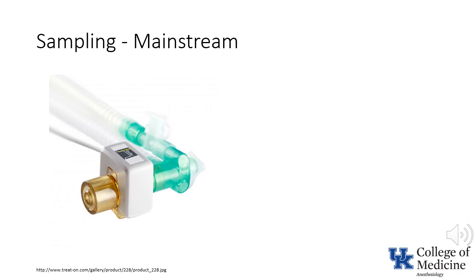The primary advantage of mainstream capnometry is the response time — you see the value almost immediately. Have you ever held your breath waiting for a CO2 waveform after a particularly difficult intubation? You wouldn't have to wait so long if mainstream sampling was used. The primary disadvantage is that the measuring device, attached to the circuit, has some weight and tends to pull the tracheal tube out unless properly supported.